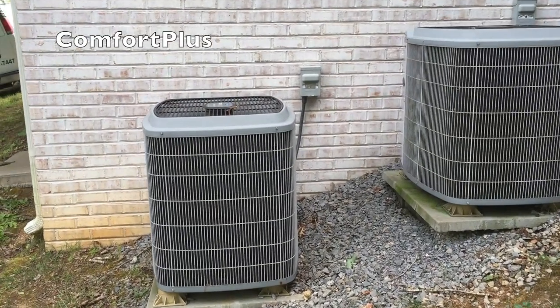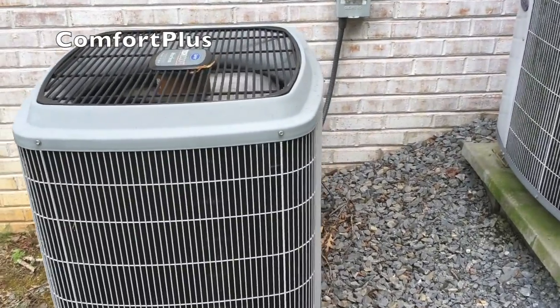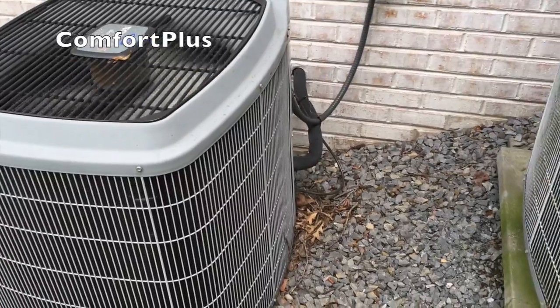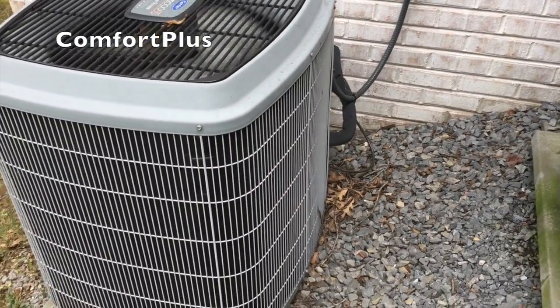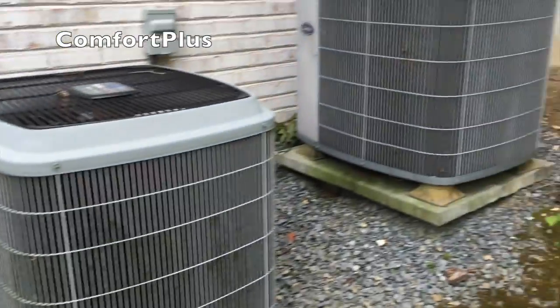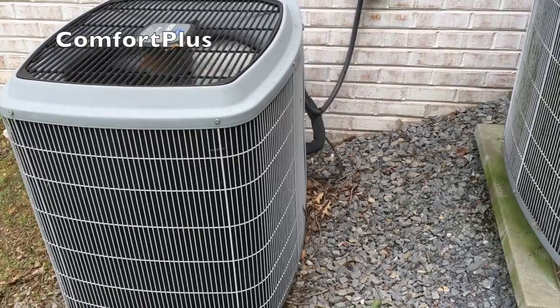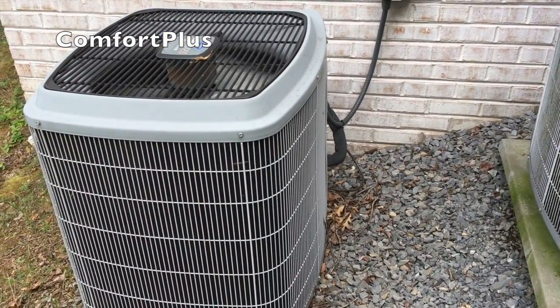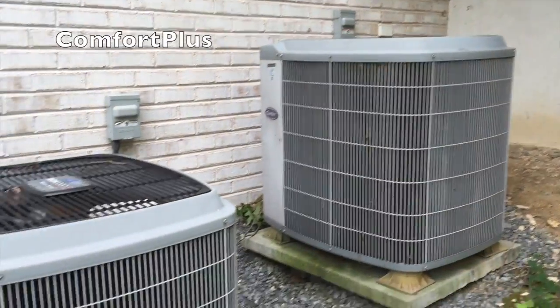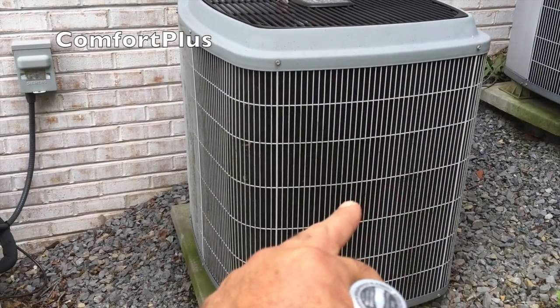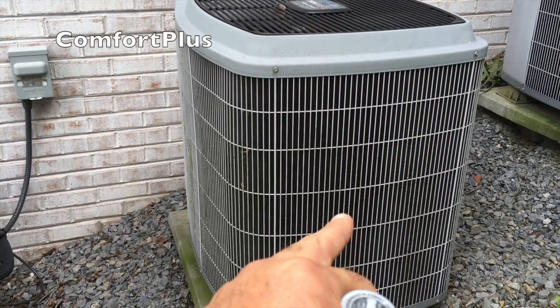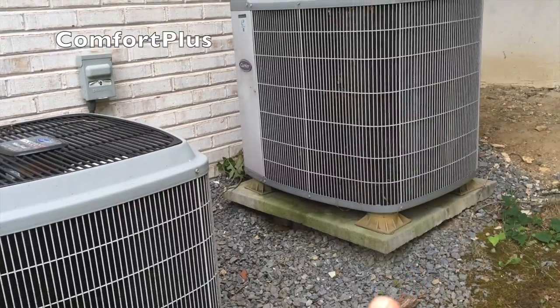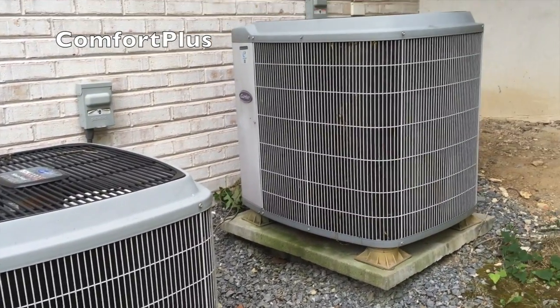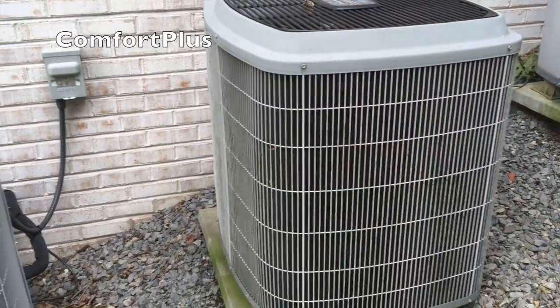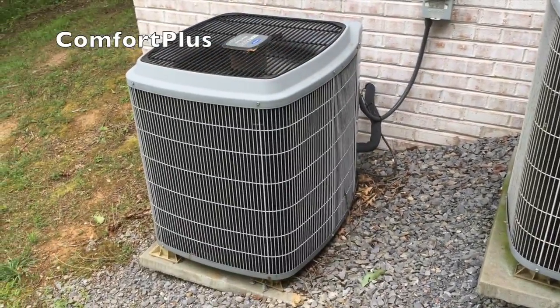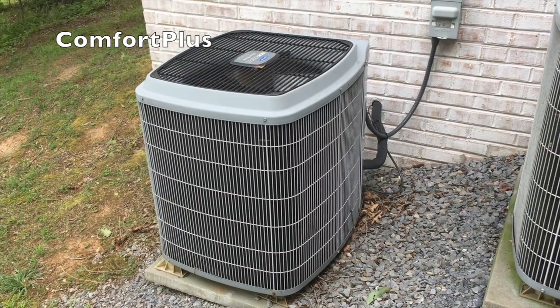Okay, I'm gonna go ahead and pump this one down, so I can cut the air handler loose on the inside. I just turned it on inside, so I won't have to fool with opening up the cover or anything right now. It's actually got less use on it than either of these other two, so I will pump it down, seal the ends up good, and store it somewhere for when one of these others go out. Probably what I'll do, this one will be my garage unit, which I won't use all that much, but that one does the upstairs. I'll probably replace it next, and then if nothing happens before then, I'll have 2 extra ones for the garage. So I should be set as far as R22 2-ton heat pumps for a little while.